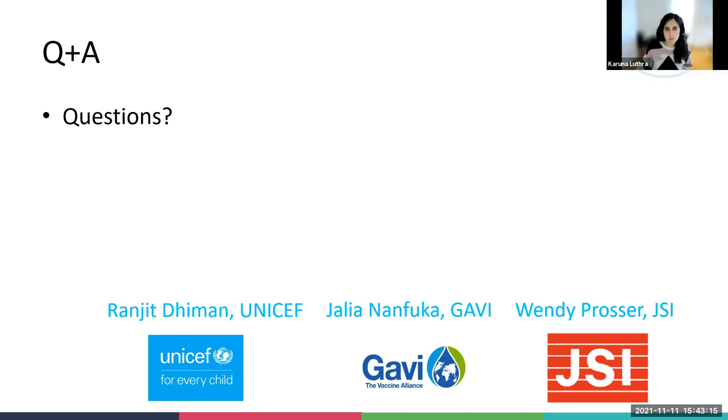I can add to this as well. Sometimes the equipment may no longer be pre-qualified because the manufacturer has discontinued making it because they've made a new model. So it may not necessarily reflect that there's something wrong with the equipment. It may just mean that the manufacturer has a new upgraded model and is choosing not to produce that model anymore, or choosing not to renew its pre-qualification. So you shouldn't necessarily assume there's a problem with the equipment. As Ranjit was saying, it's best to get clarity as to why that specific equipment is no longer considered pre-qualified.